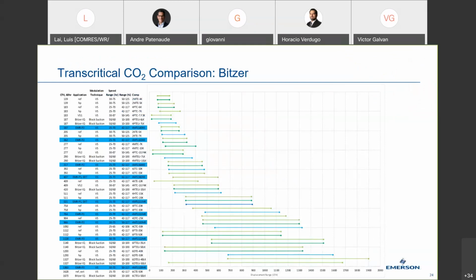So if we look at Bitzer only, forget the others I just showed you. Bitzer's all in green, Emerson's all in blue. The light green is the standard refrigeration motor version that Bitzer uses. The dark green is a heat pump version, which has a different motor. So right away, they double the sizes because they've got two motors. So keep that in mind. There's another thing. They do have a model as well that has a variable speed component built right onto the compressor, similar to our small little recips, the little Embraco. The drive's already on there kind of thing. So they have that.